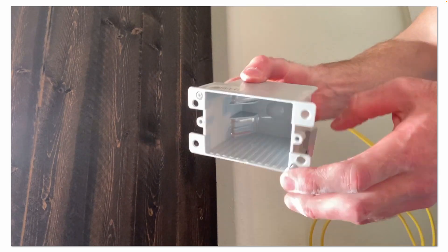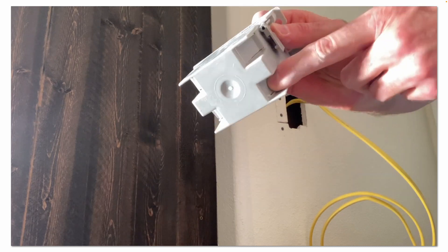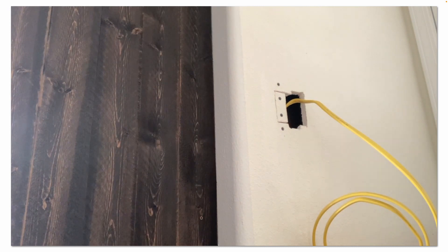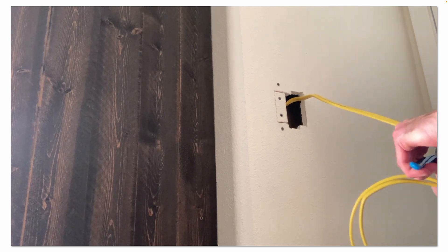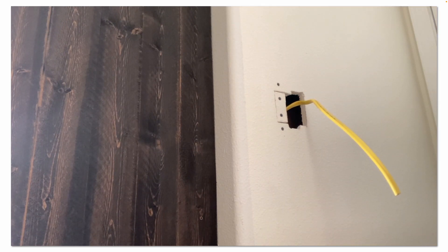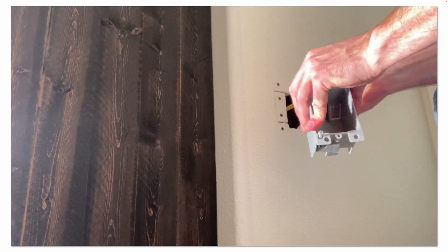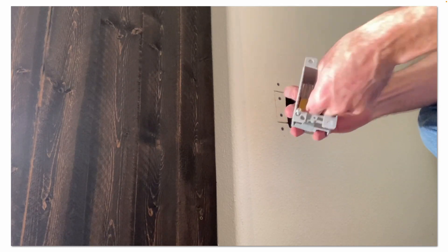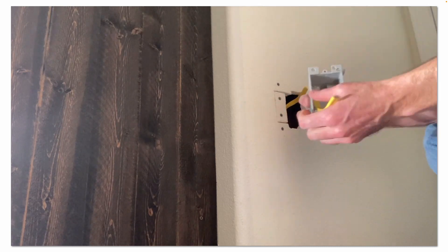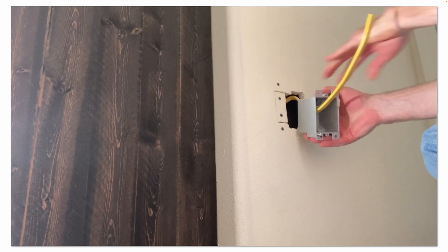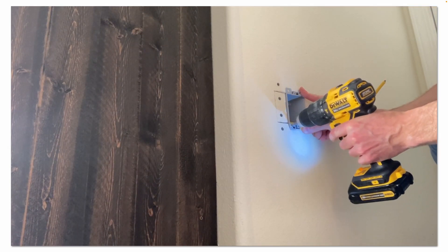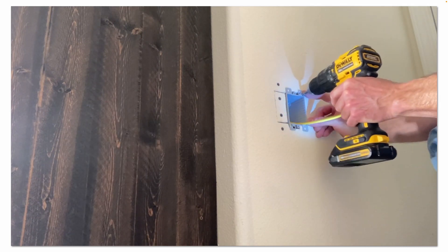All right, so you see there's little plastic wings on the box. When you tighten those Phillips head screws, the wings will grab the back of the drywall. Now we'll go ahead and feed our Romex cable into our new box. Just want to cut it to the proper length that I need. You need to make sure the cutout and the drywall will accommodate those little plastic wings. That's why you'll note the shape of my cutout is sort of a zigzag shape, it's not a perfect rectangle. Pull the Romex through your box, gently push the box in, and then very gently tighten those screws down. Remember it's a plastic box with plastic tabs or wings, you don't want to snap or break anything.